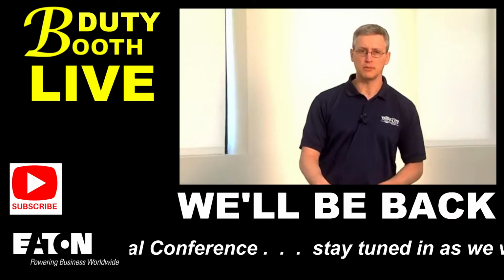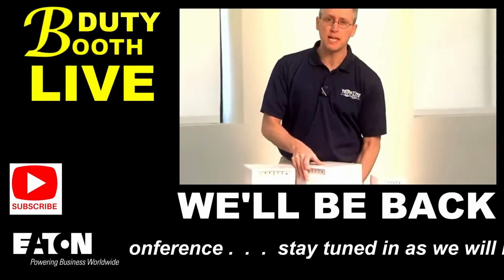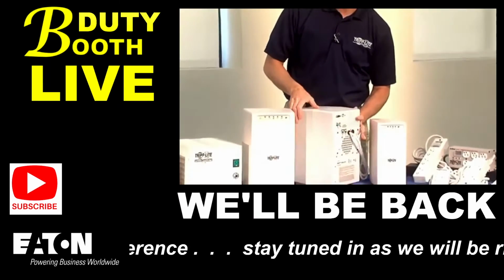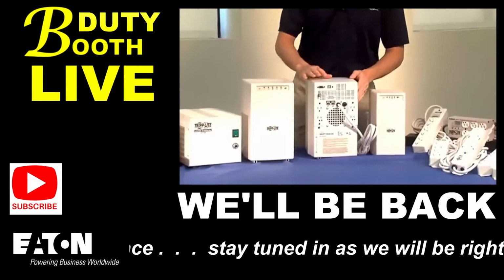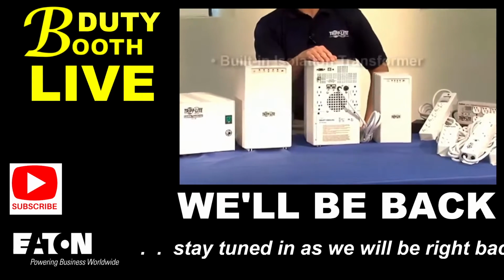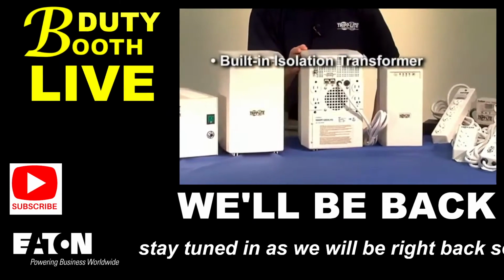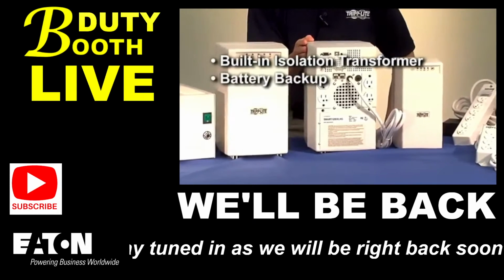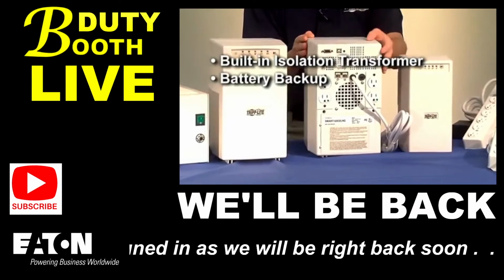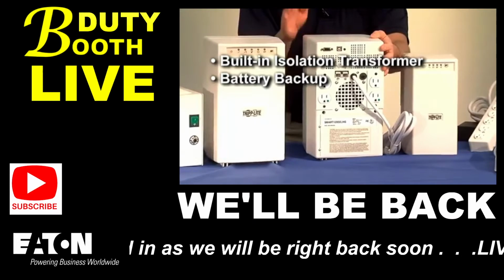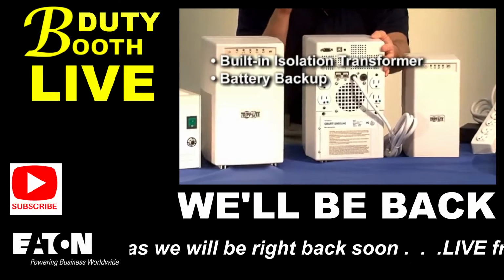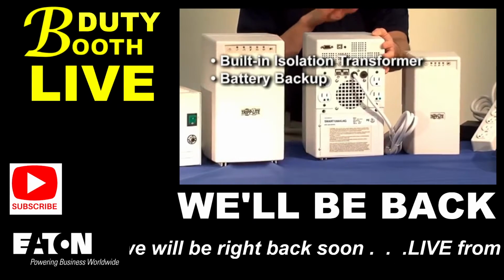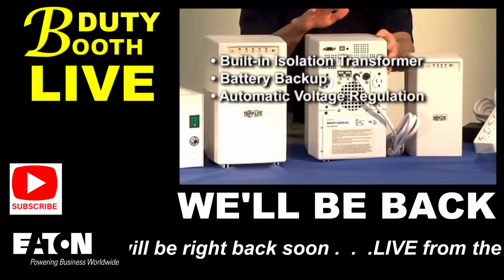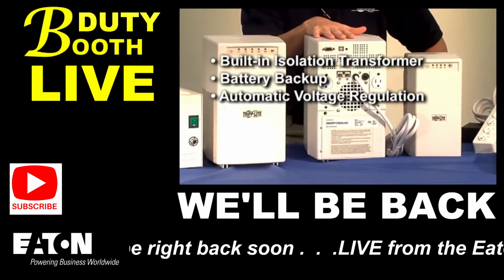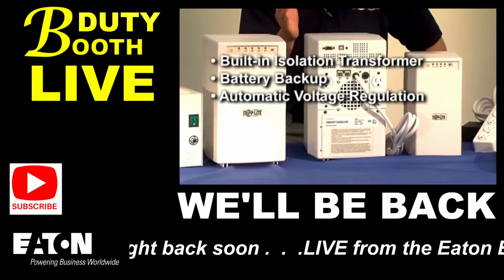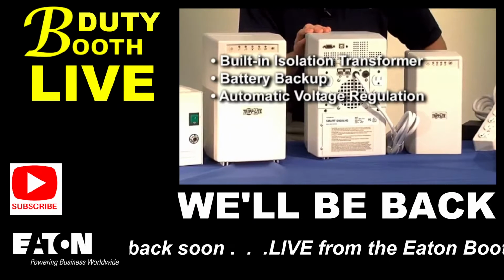Let's look at a few examples. This is a Tripp Lite medical grade UPS system. To ensure compliance, it features a built-in isolation transformer. To guard against downtime, it provides battery backup during blackouts, bridging the gap between utility power failure and facility generators engaging. Automatic voltage regulation supports equipment through low or high voltage indefinitely without using battery power.